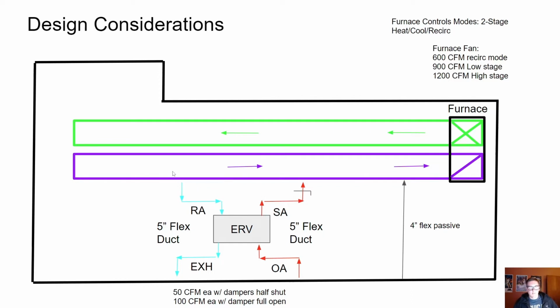So as you can see, on the far end of your return duct, where the air is just starting to come in and go back to your furnace and then get recirculated, you tap into that return duct and duct it to the ERV.